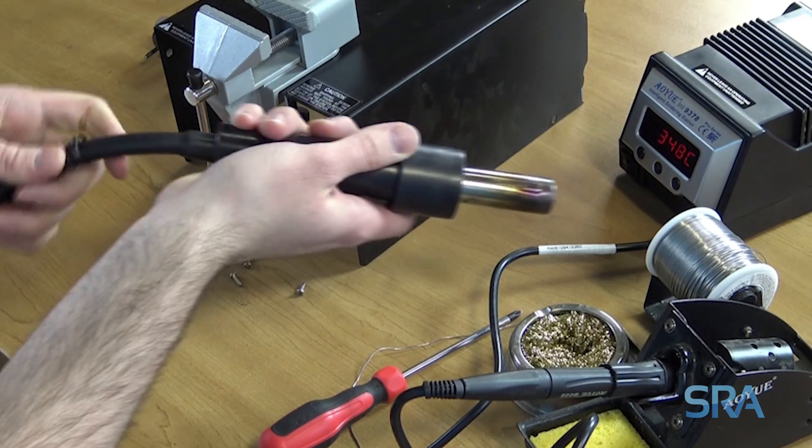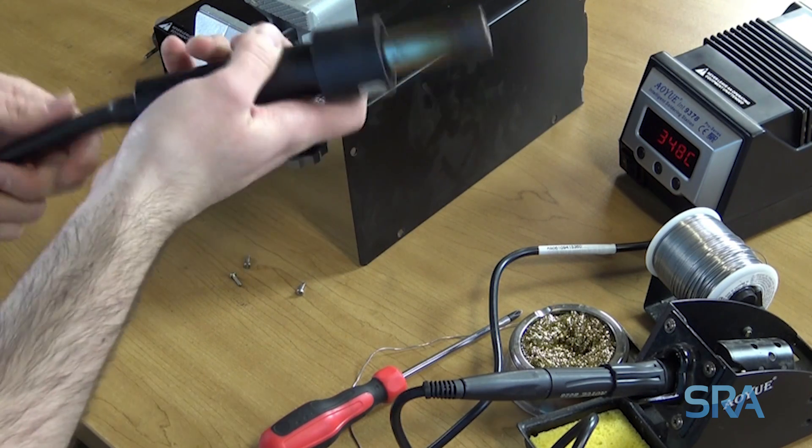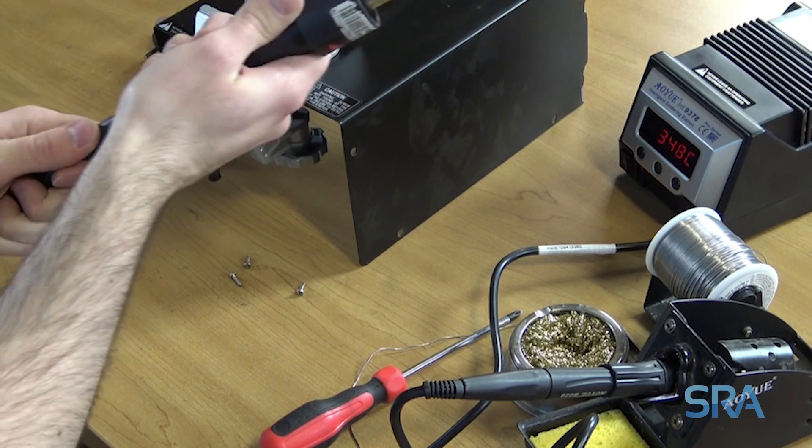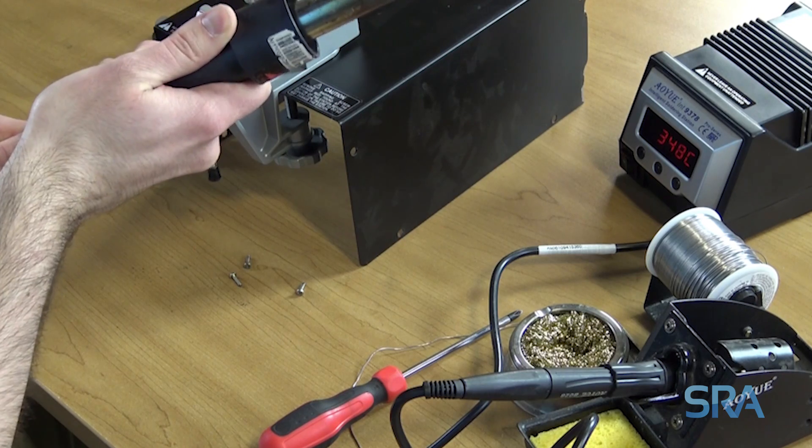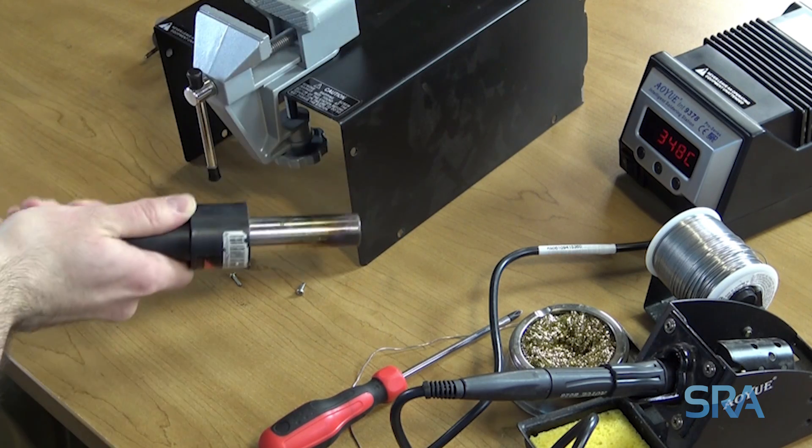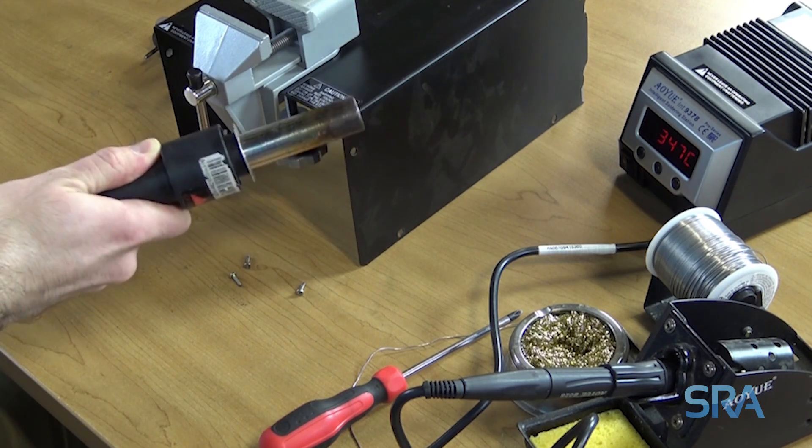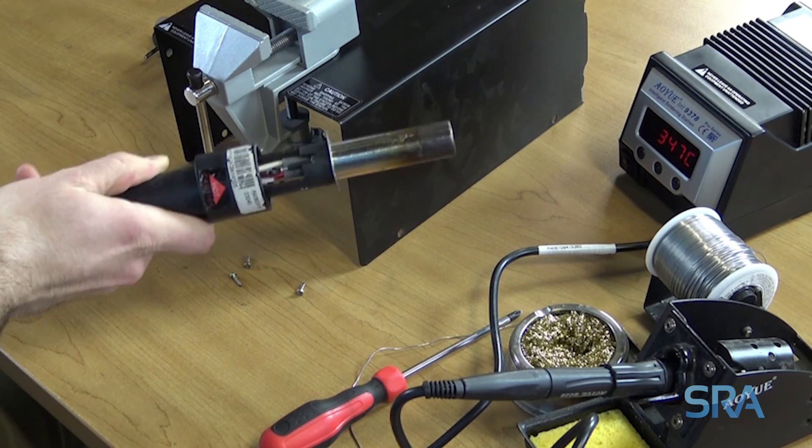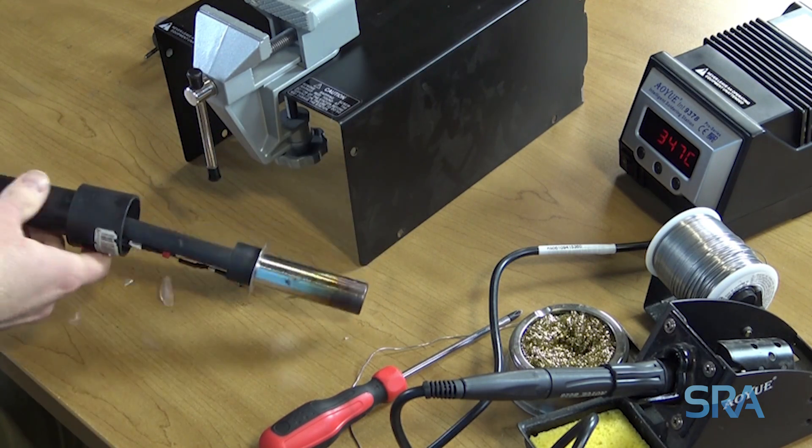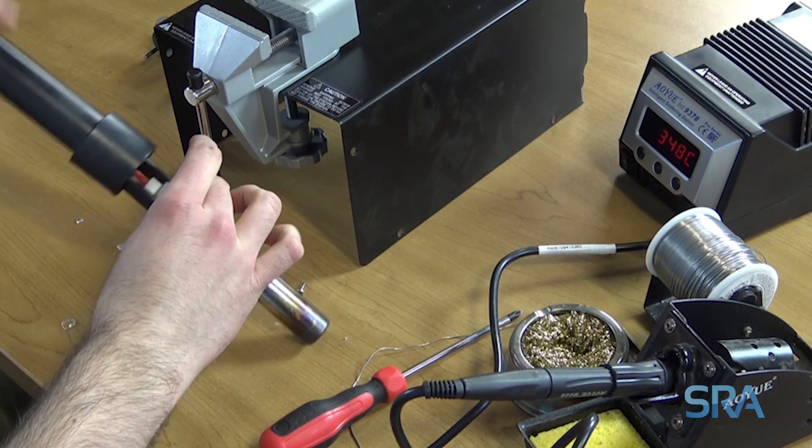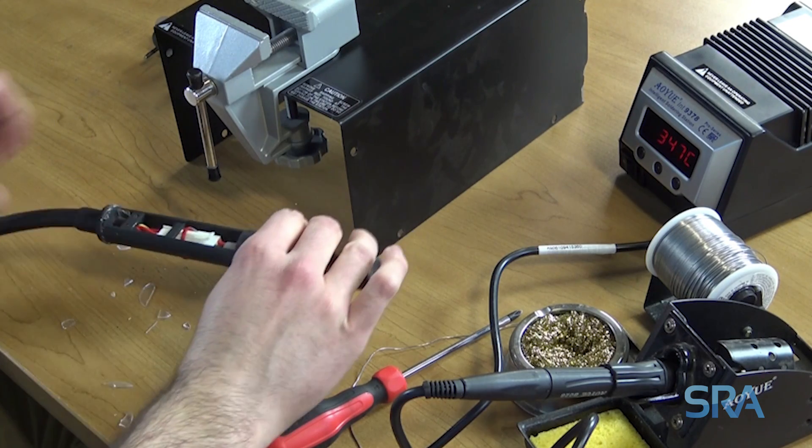We're going to take the strain relief off the cable and push up on the tube to reveal the inside. We have a broken heat tube here. There's a lot of glass debris.